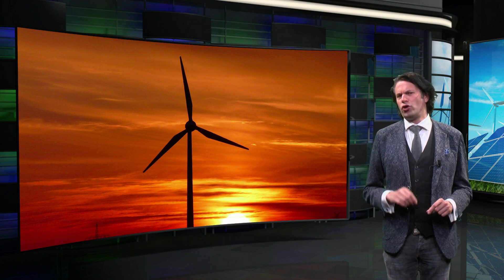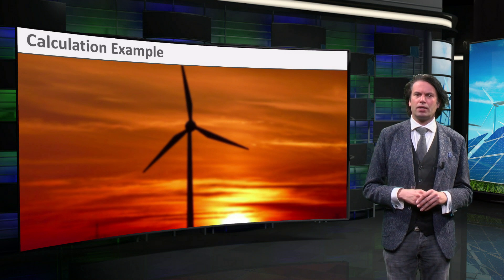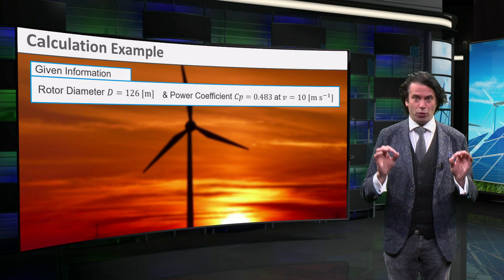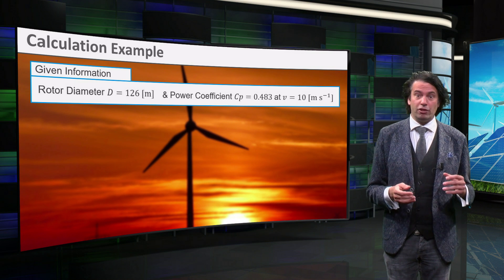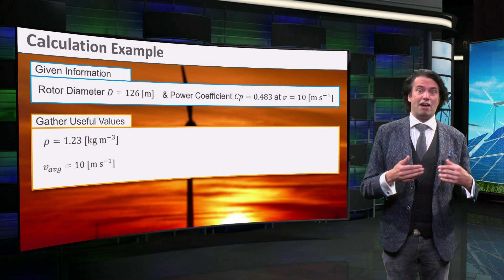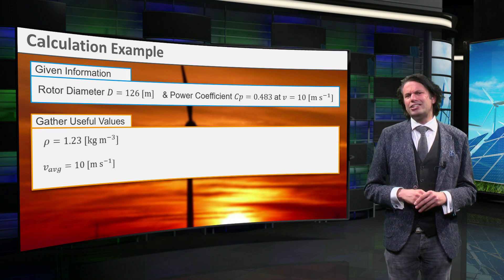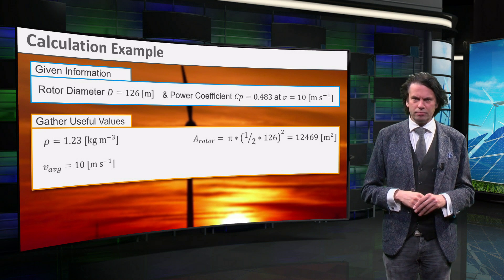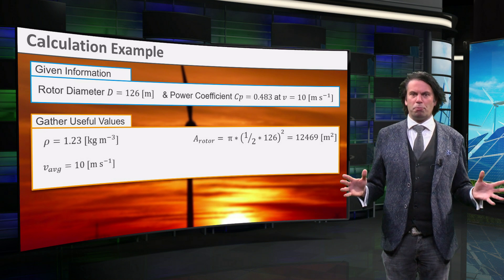Let's use what we have learned so far. We will take the Enercon E-126 wind turbine as an example. It has a rotor diameter of 126 meters and a power coefficient of 0.483 at a wind speed of 10 meters per second. First of all we need to gather the appropriate values. The density of air is 1.23 kg per cubic meter. Furthermore, we will assume 10 meters per second as an average yearly wind speed at the location of our Enercon turbine. Now we will only need to determine the frontal surface, which is pi times half the diameter squared. This results in approximately 12.5 times 10 to the power 3 square meters.